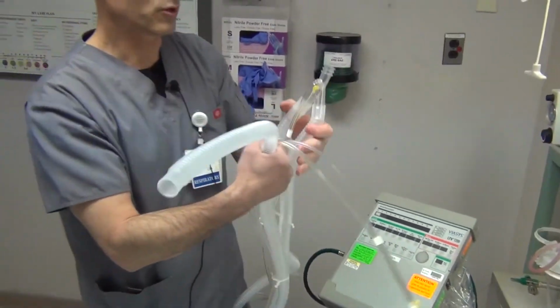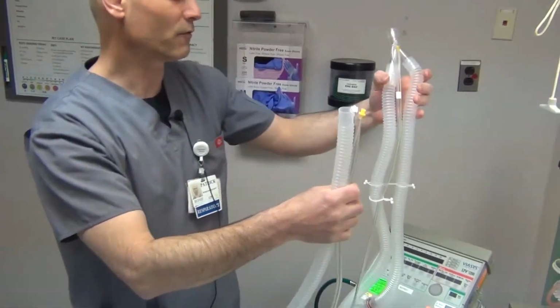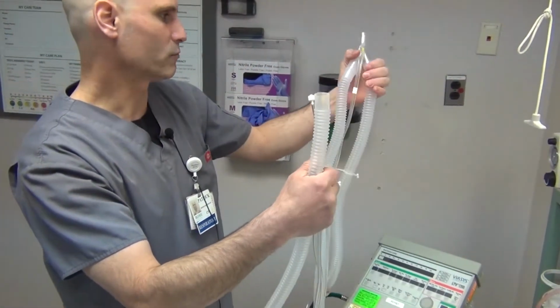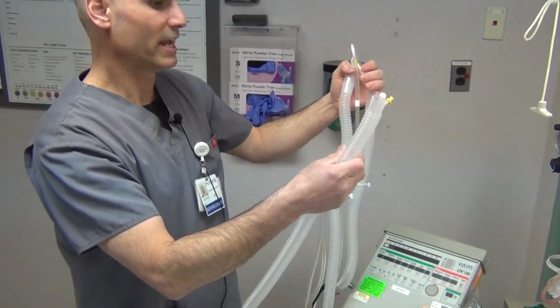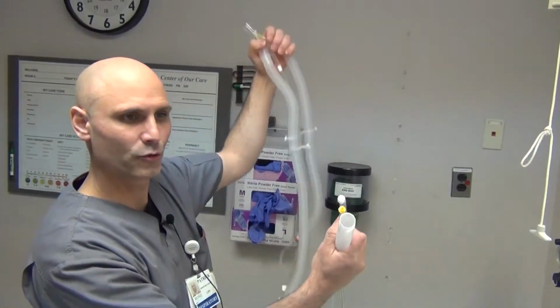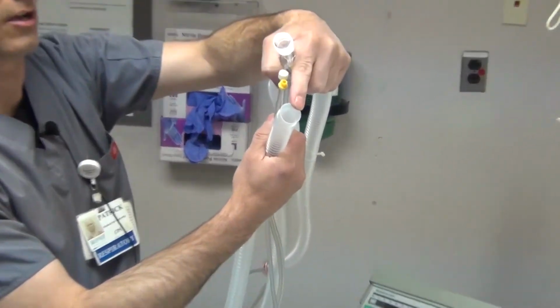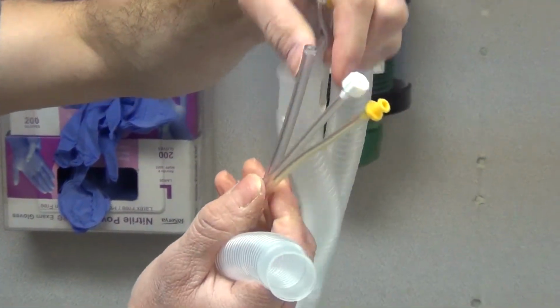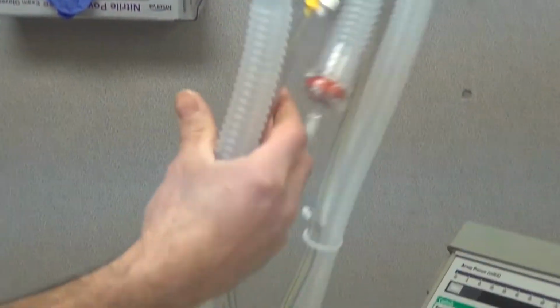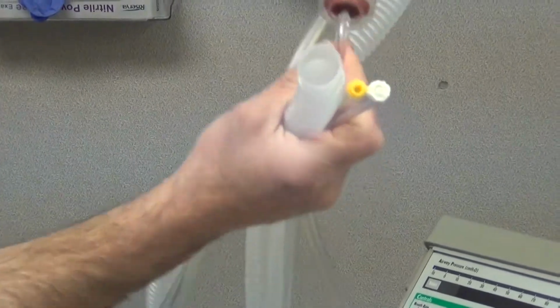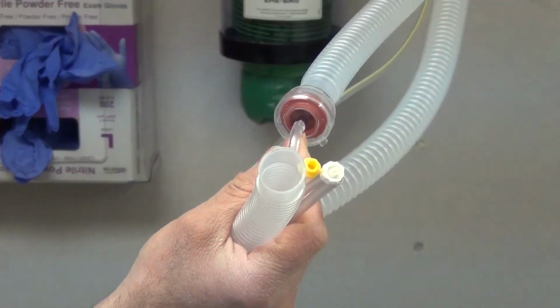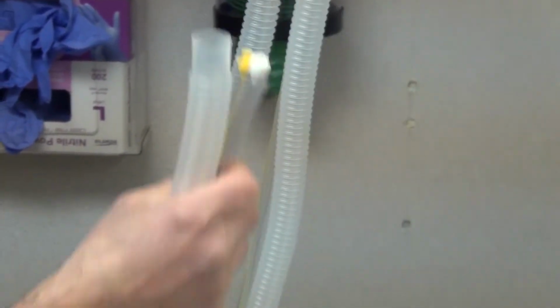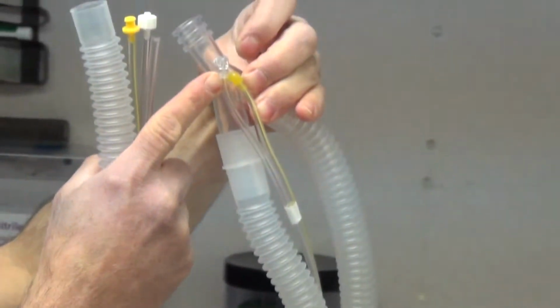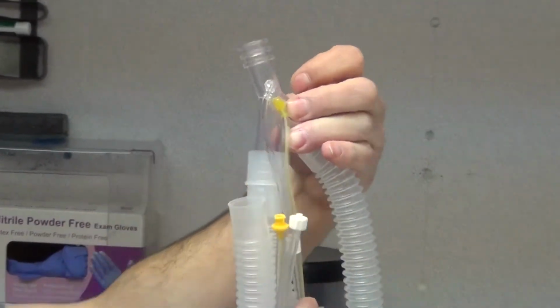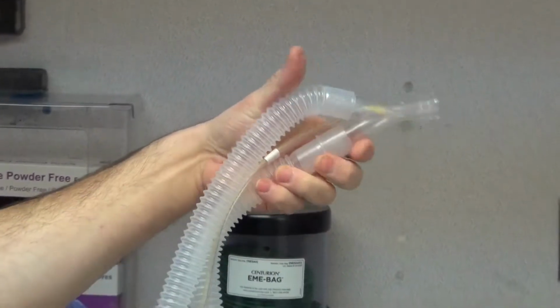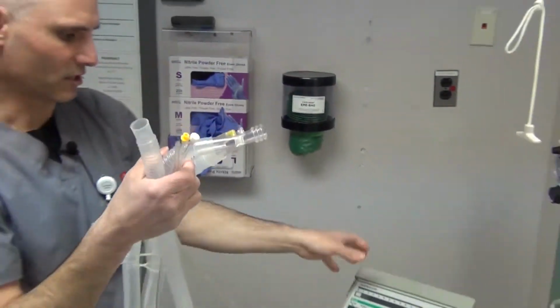If you saw the previous video on the Puritan Bennett 840, you noticed the circuit was blue. This one is clear. It also doesn't have two large tubings at the end. It has one large and three little tubings, and if you follow those three little tubings, it comes to the end of this one, which is your exhalation valve, and then the other tubing comes up to here, which measures pressure and monitors what's going on. So setting it up is a little different.